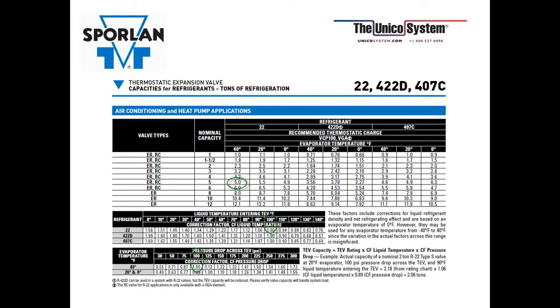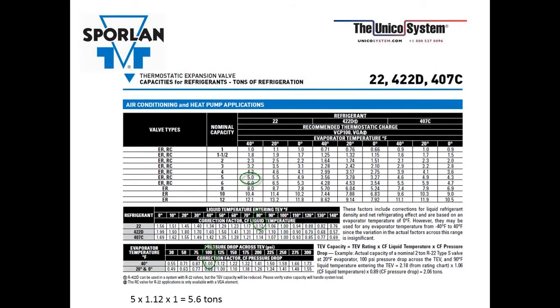But if you change any of those parameters, the capacity will change, which the next few slides will show. Here we're using the same 5-ton nominal ER valve. The evap temperature is still 40 degrees, but we've lowered the liquid temperature to 80 degrees. So now the correction factor is 1.12. In other words, you're getting 12% more capacity. We let the pressure drop stay the same at 100 psi. So you multiply it out, and that 5-ton valve is now 5.6 actual tons.